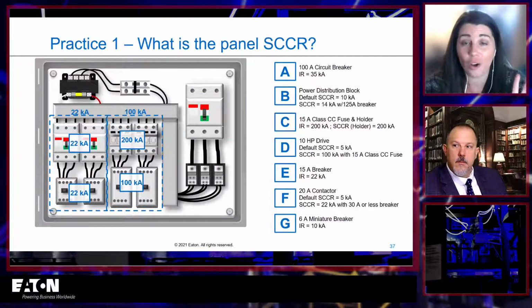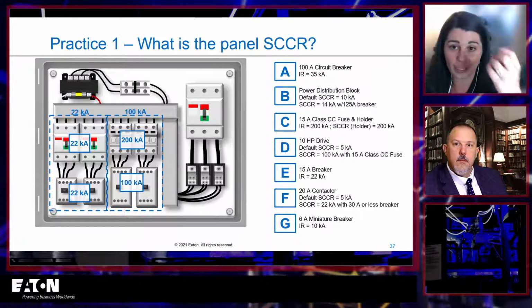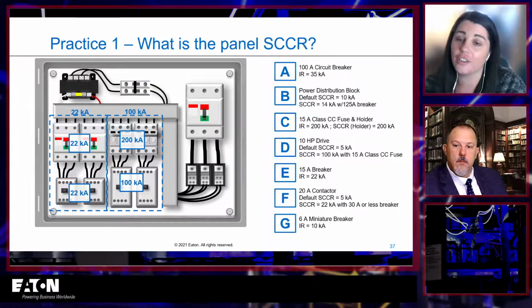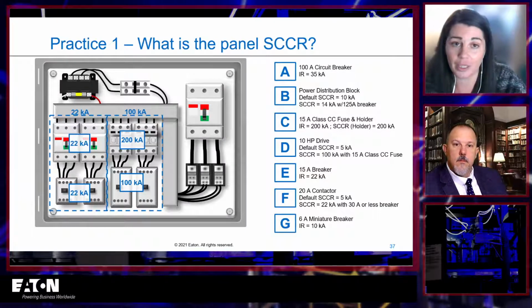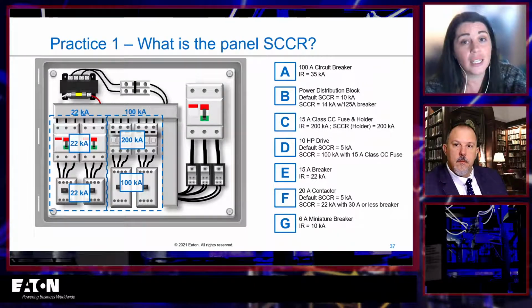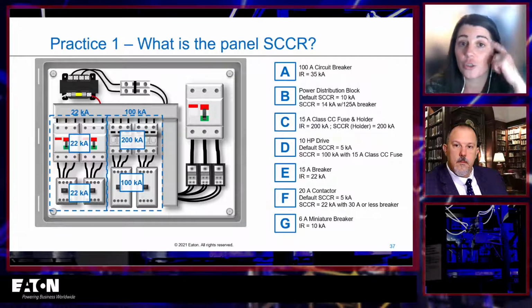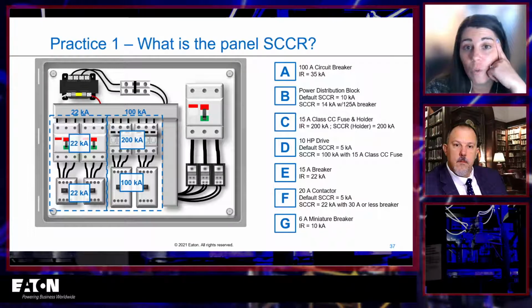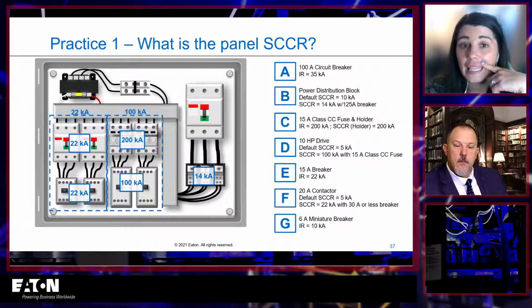In reality, the hardest part of all of this is actually looking up those ratings sometimes, finding the documentation and figuring out what they are. Sometimes it's the most time-consuming part of this whole process. Step two is to determine the short circuit current rating for any device in my feeder. The only device here in my feeder that's going to have a short circuit current rating is this power distribution block B. So it has a default rating of 10 kA, or it's 14 kA with a 125 amp breaker.